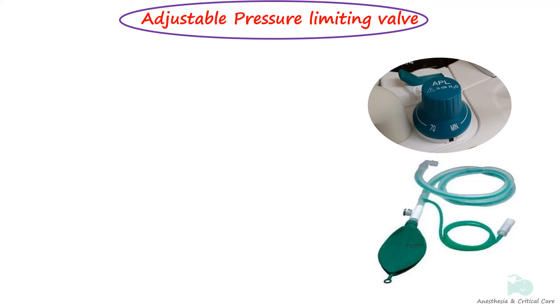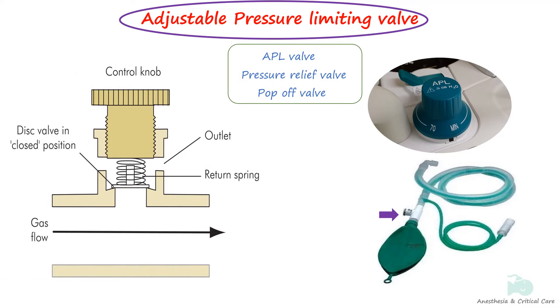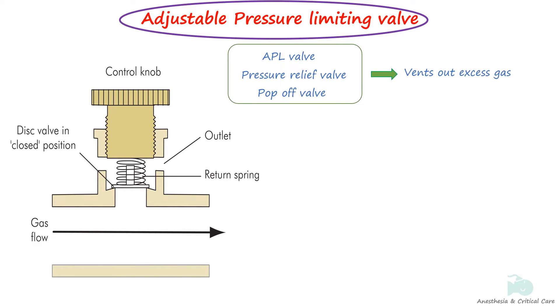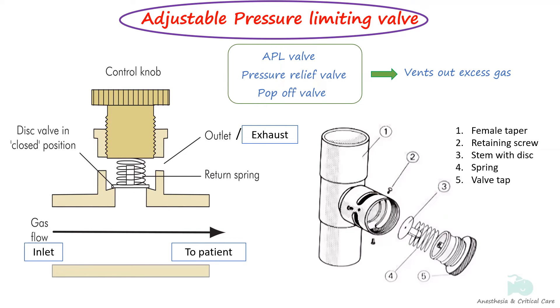The adjustable pressure limiting valve, also called APL valve, expiratory valve, pressure relief valve, or pop-off valve, are spring-loaded devices that vent out gases when excess pressure builds up. They typically have three ports: the inlet, which brings in fresh gas flow; the patient port, which takes gas to the patient; and the exhaust port or outlet, which vents out excess gas to reduce pressure buildup. The individual components of such a valve are also shown here.